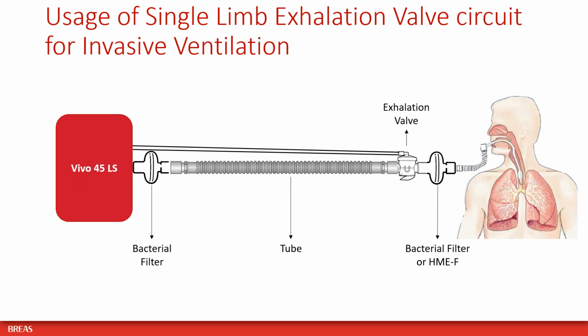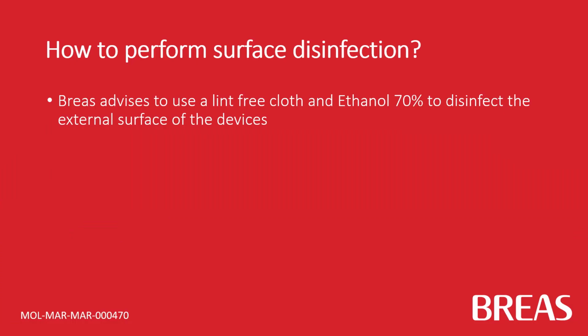When using a single limb circuit with active exhalation valve for invasive ventilation, place a bacterial filter at the air outlet of the ventilator and a bacterial filter or HME with filter between the active exhalation valve and the patient. Breas advises to use a lint-free cloth and ethanol 70% to disinfect the external surface of the devices.